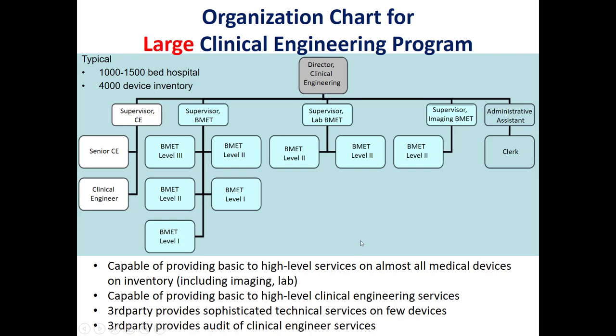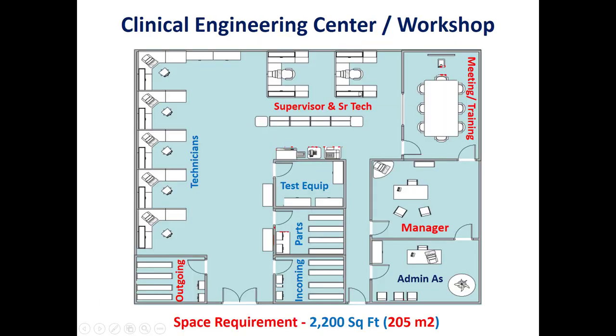Here we can see a drawing for a clinical engineering workshop or center. It includes an area for incoming and outgoing medical equipment, a storage area for spare parts and testing equipment, working areas for clinical engineers and biomedical technicians, offices for supervisors of both teams, an office for the manager and director as well as administrative assistants, and a meeting and conference room for training and meetings.